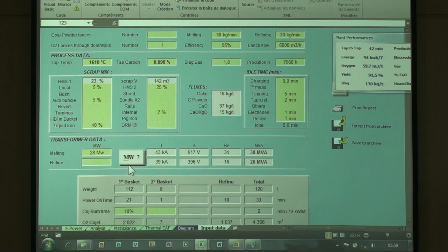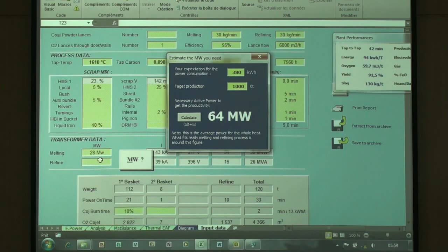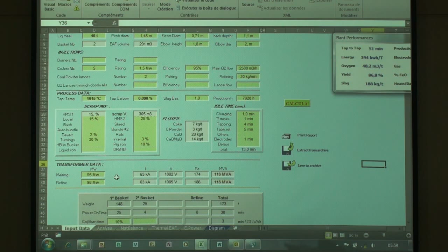On this version, you see, I had this button to calculate directly the megawatts. I mean, I know that the furnace is going to use 380 kilowatt hours per ton. I want to produce 1 million tons, so I need average 64 megawatt. Average 64. So then you know that you will type here 70 and you will see what kind of productivity you get out of it. If you want, I can add this button here. It's not a big deal.